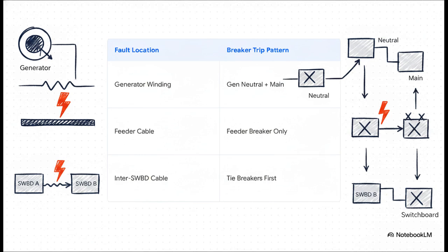But what if the fault is down a feeder cable? Well, selectivity dictates we trip only that specific feeder breaker. The generators and the main bus bar stay perfectly online, and the ship keeps moving. Finally, if the fault is in an inter-switchboard tie cable, the golden rule is to trip the tie breakers first.